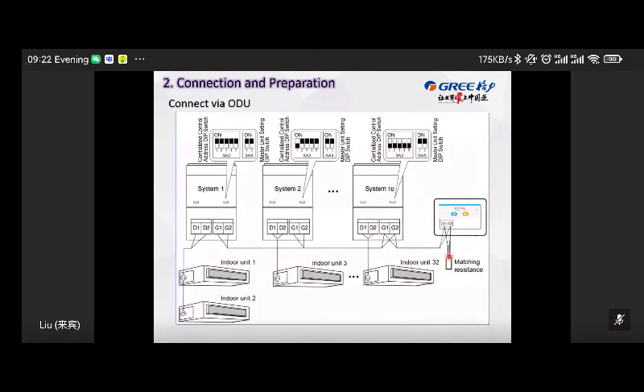The second one, connect to the outdoor units. If there are multiple systems you want to control by one central controller, connect to the G1, G2 terminal. And also just remember, for different systems, there should be an address setting. You can operate on the SA2 system address setting to differentiate each system and avoid address conflicts. Okay, that's the second wiring method.